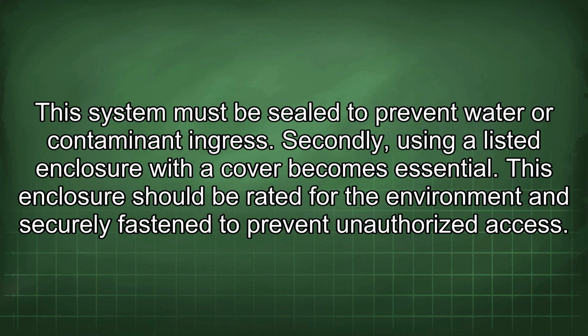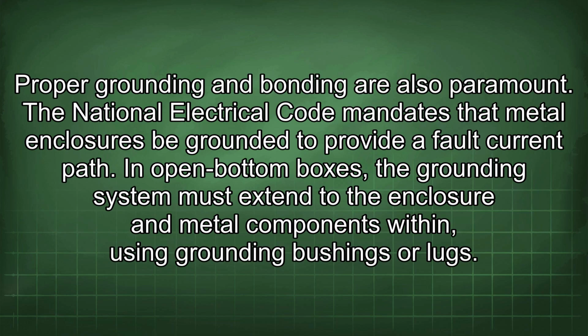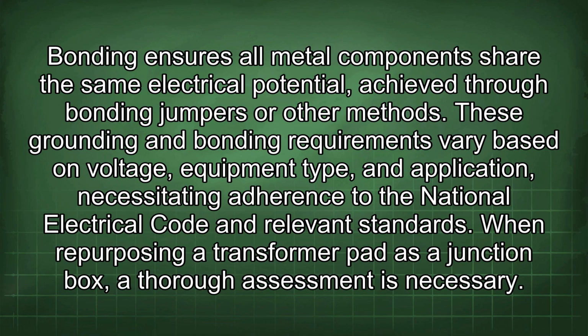Secondly, using a listed enclosure with a cover becomes essential. This enclosure should be rated for the environment and securely fastened to prevent unauthorized access. Proper grounding and bonding are also paramount. The National Electrical Code mandates that metal enclosures be grounded to provide a fault current path. In open-bottom boxes, the grounding system must extend to the enclosure and metal components within, using grounding bushings or lugs. Bonding ensures all metal components share the same electrical potential, achieved through bonding jumpers or other methods.